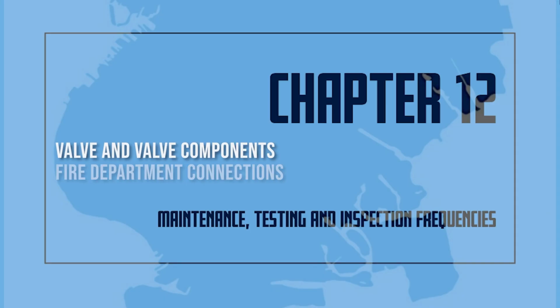Control valves. All indicating valves controlling water supply shall be sealed, locked, or provided with other approved methods as outlined in the National Fire Protection Association No. 25, 2002 edition. A seal is defined as an easily removable device, with no key required, that will indicate the unauthorized operation of a valve. Using this method shall require weekly inspections of each valve by the certificate of fitness holder.